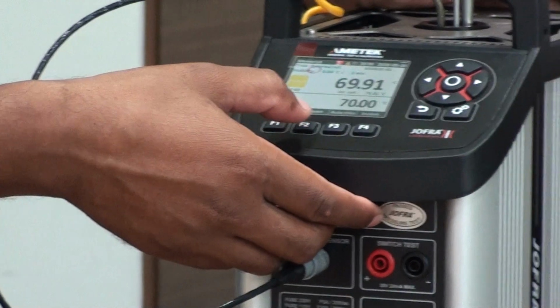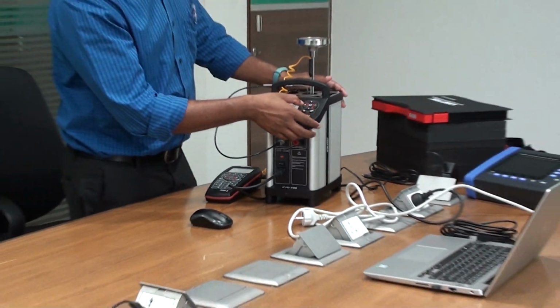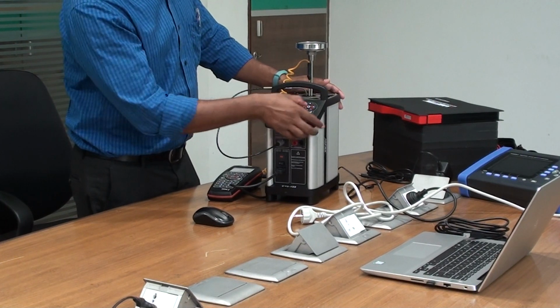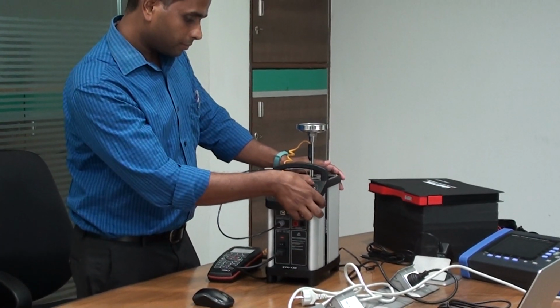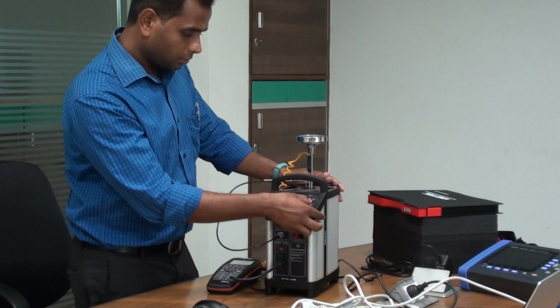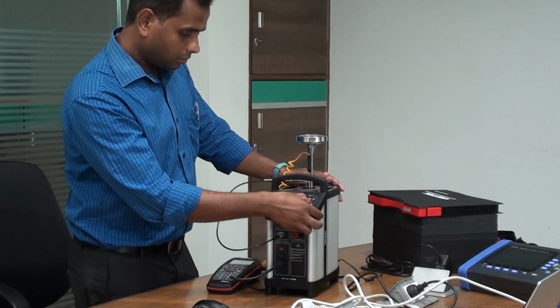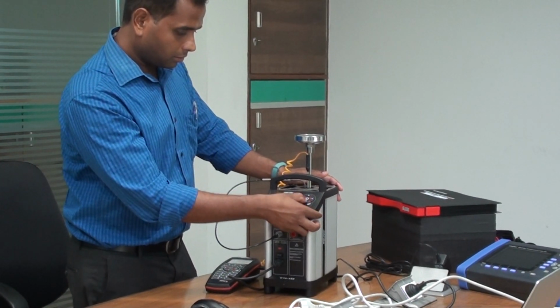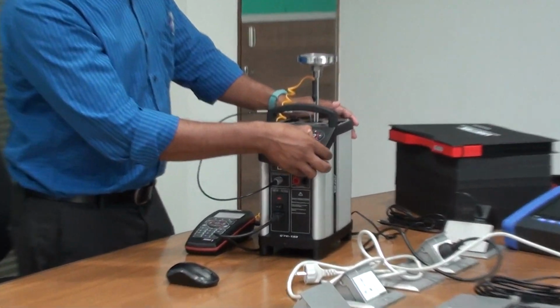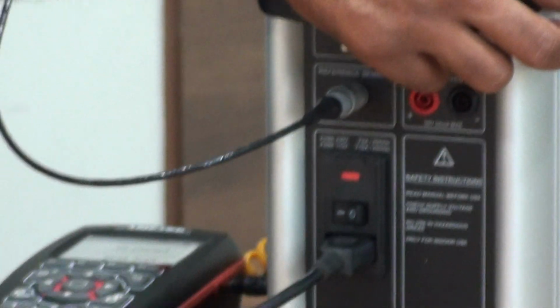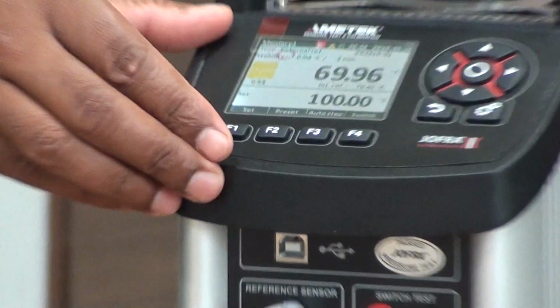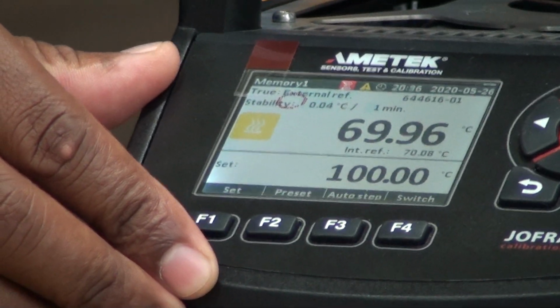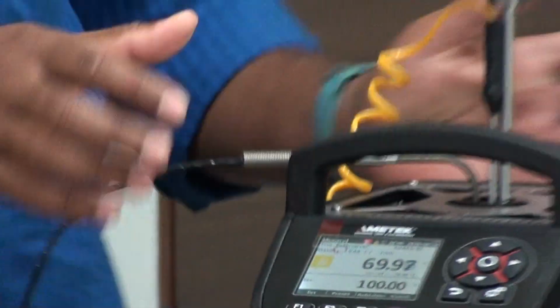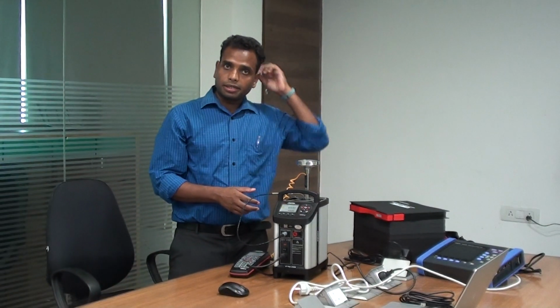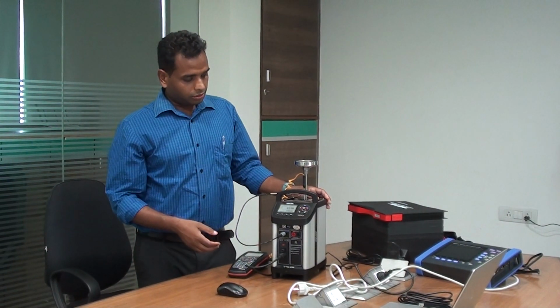Now we'll set for the next step. We'll set 100 degree. We'll see what is the maximum error that comes out. Now I have set 100 degree. It will take some time to reach 100 degree because there is a heating and cooling time generally in any calibration instrument.